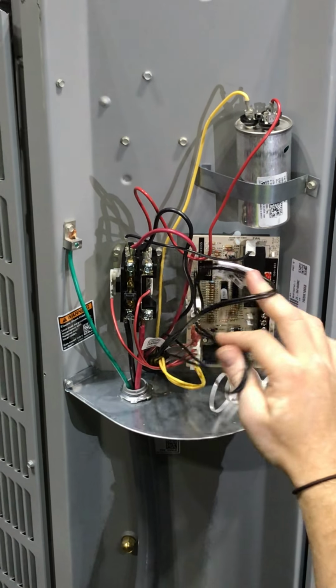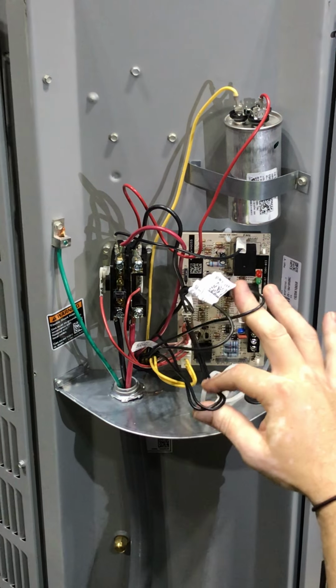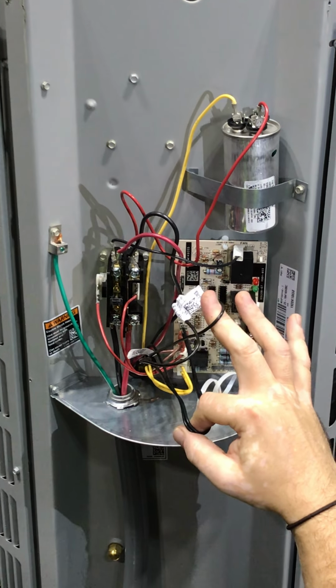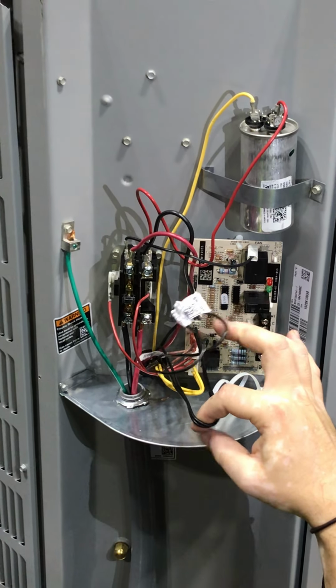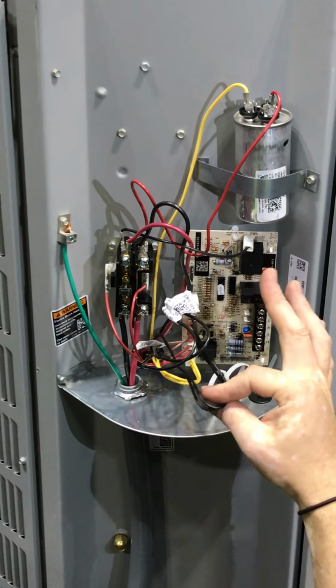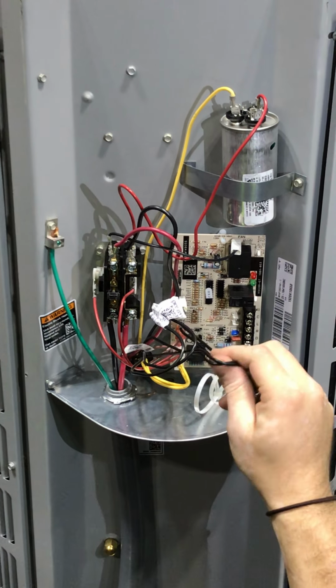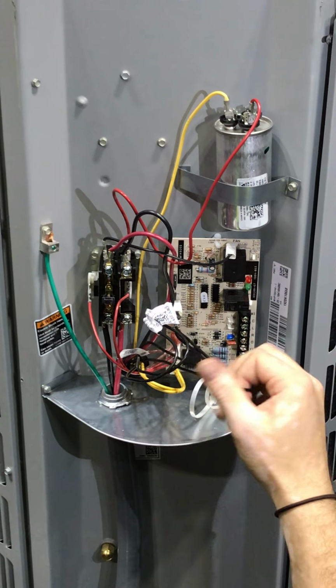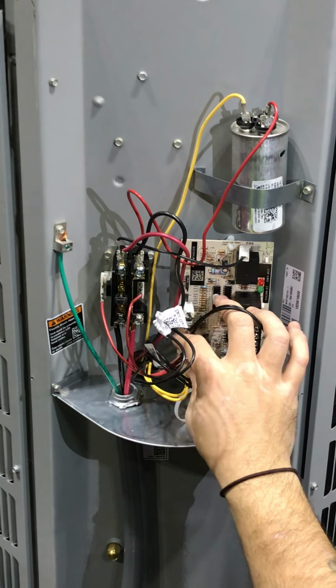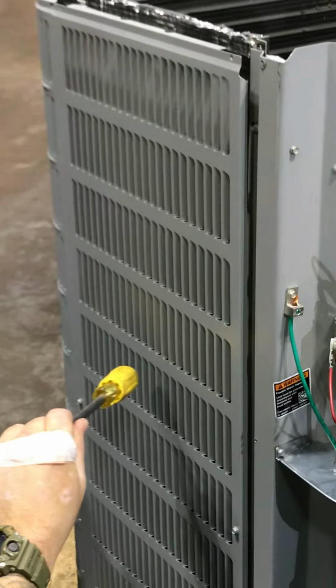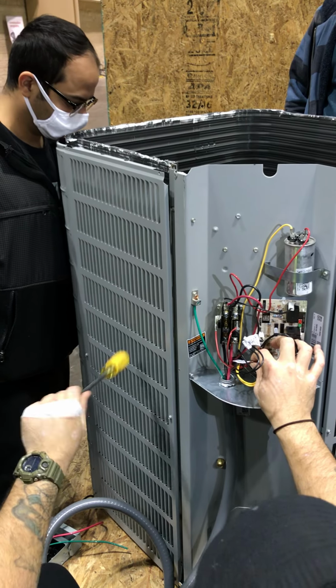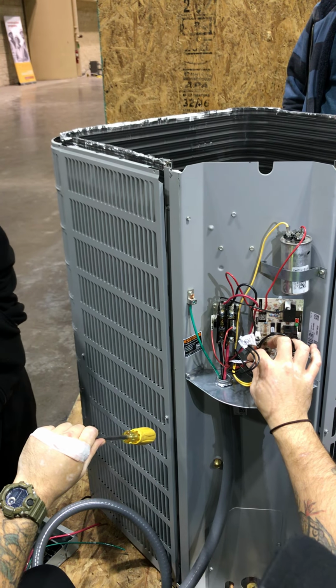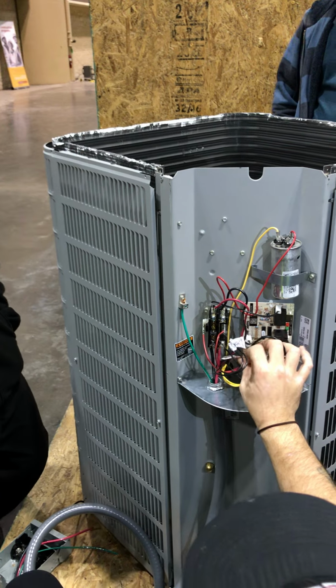All right, and then I have two more wires here. This is our low pressure transducer, that lets me know if I have enough pressure. This is your defrost right here, that goes to the coil sensor to let you know you've gotten too cold and need a defrost, because this thing gets super cold in the wintertime when you have the reversing valve on.